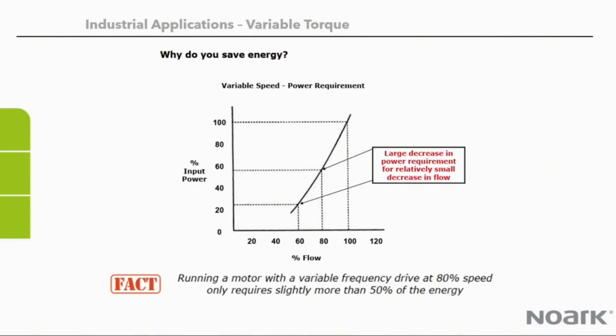How are we saving energy here? Well, in a variable torque application, it needs less torque to start, and it's a non-linear progression of speed versus energy. So we could be running at 80% of the speed, but only require about 50% of the energy to accomplish that.